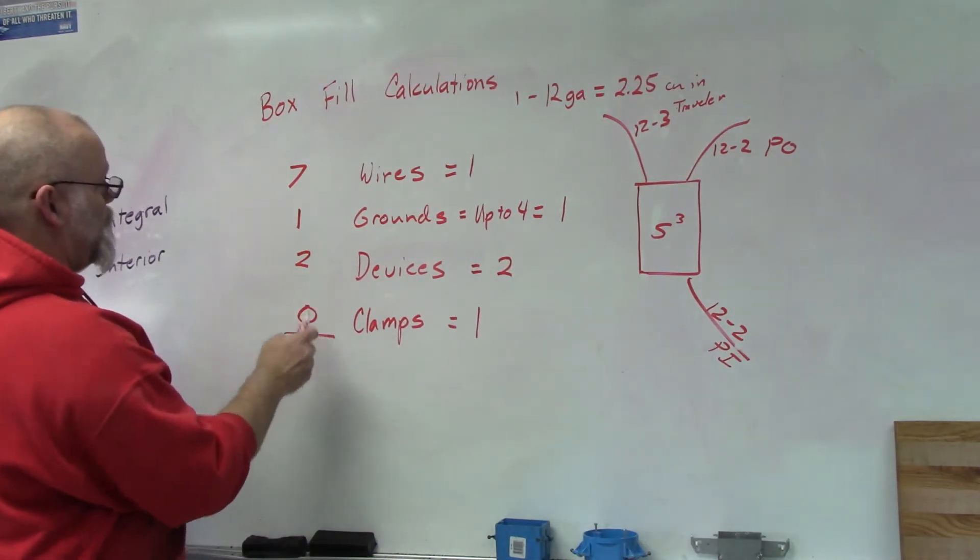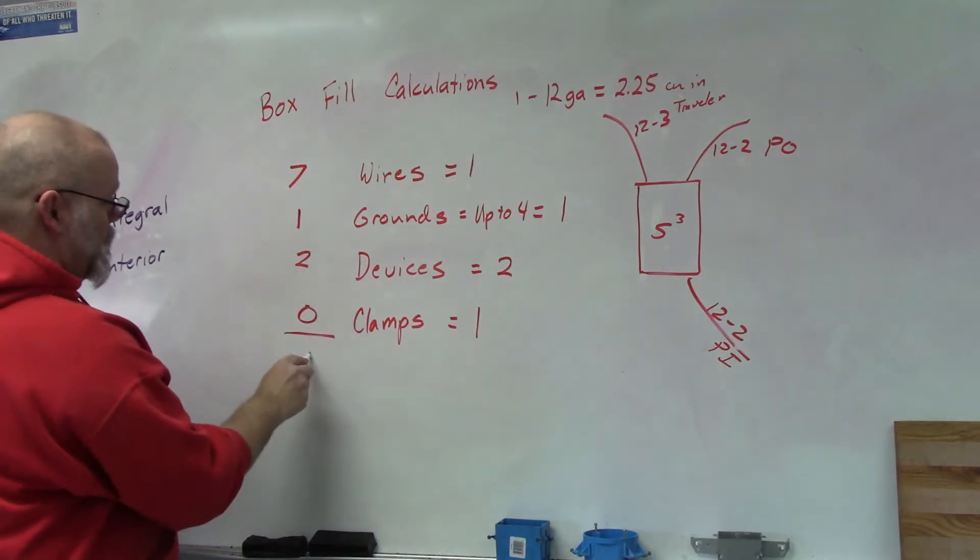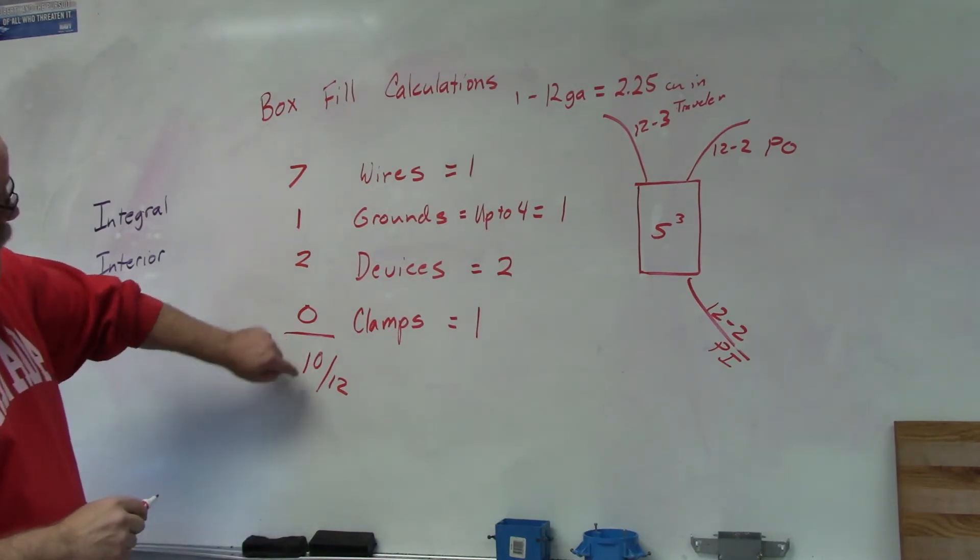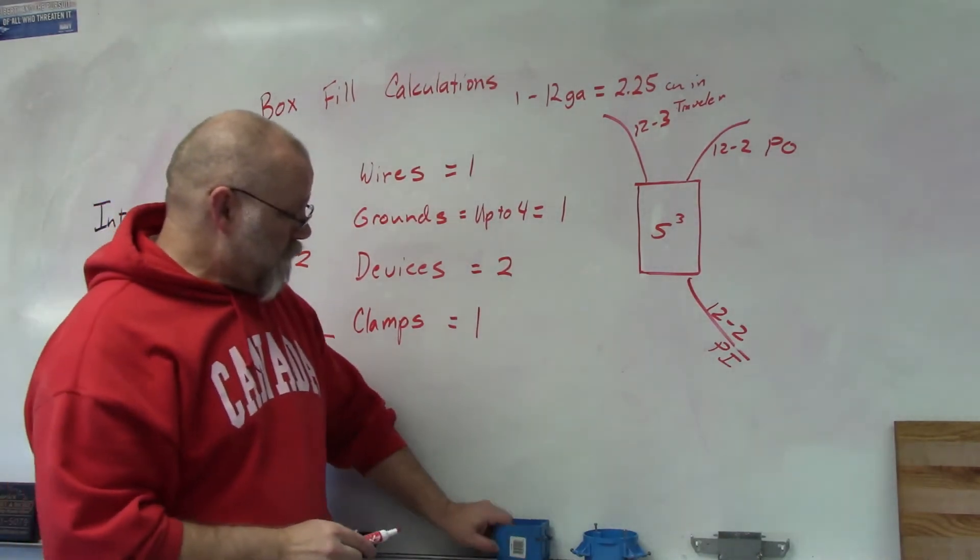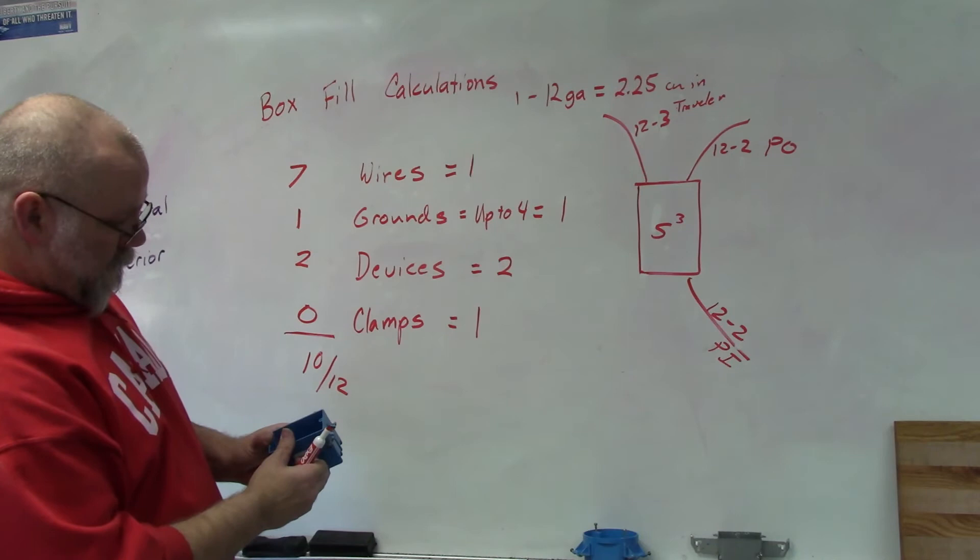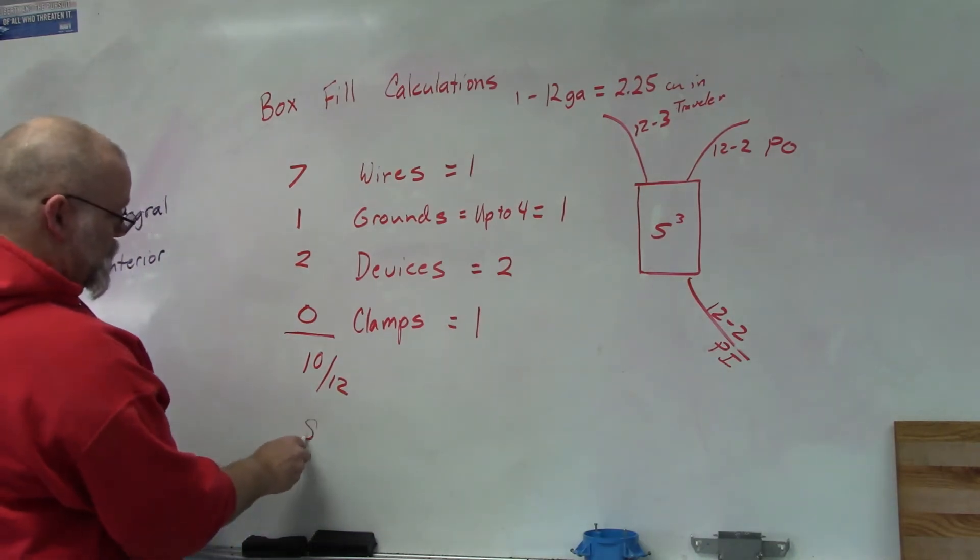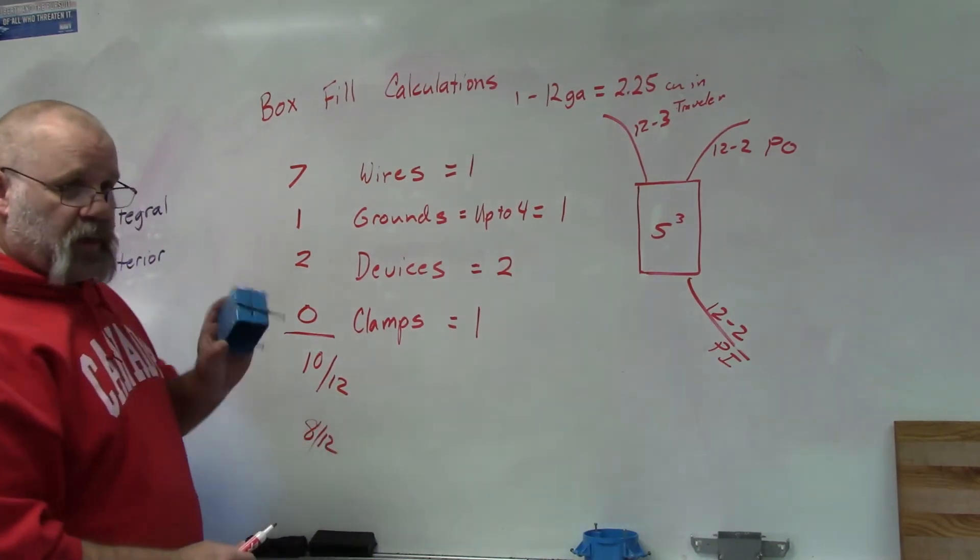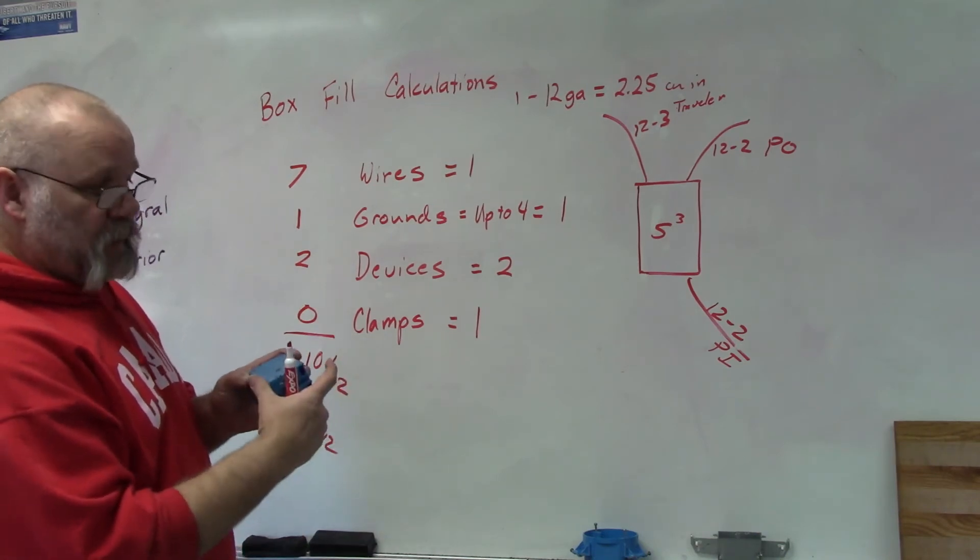So if I add this up, I got seven, eight, nine, ten twelves. So this box says that I can have eight twelves. So this box isn't big enough. It's not deep enough.